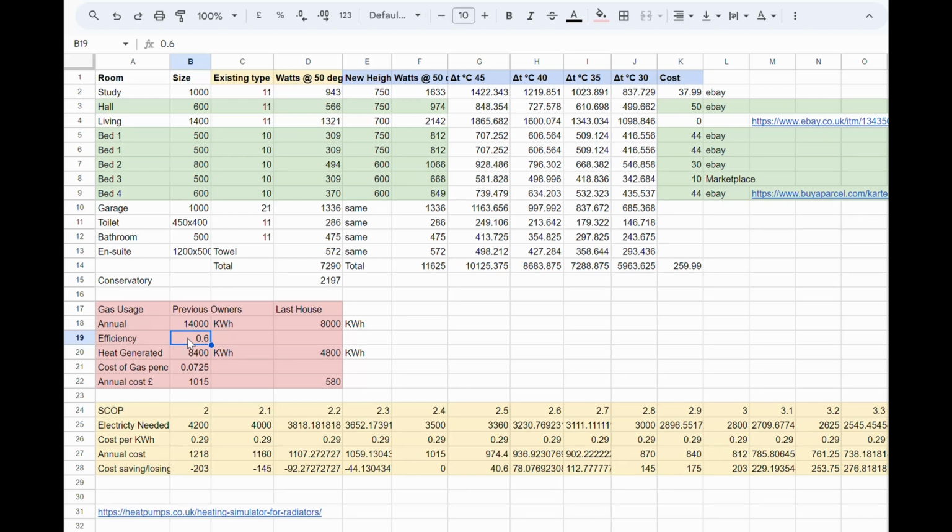We did actually then go on to find out that when they ripped out the gas boiler, the gas valve was a bit sticky, and the gas engineer, when he did his pressure loss test, found that there was somewhere between 10 to 20 millibar of gas pressure that was just constantly flowing out of our boiler, straight out of the flue, and just complete wasted energy.